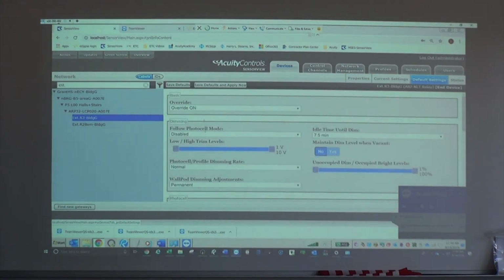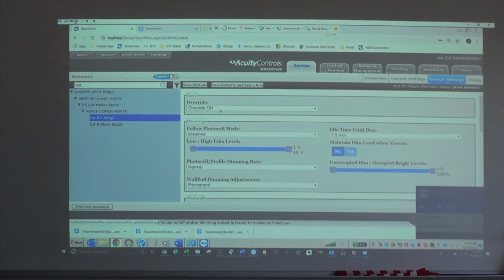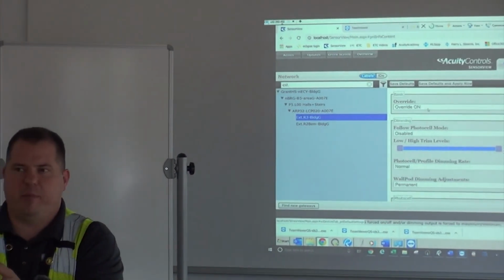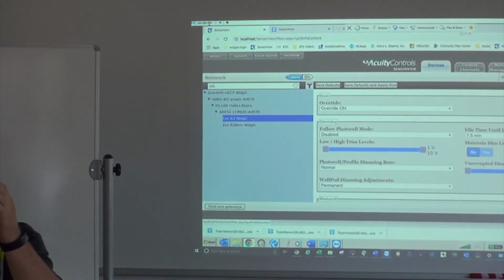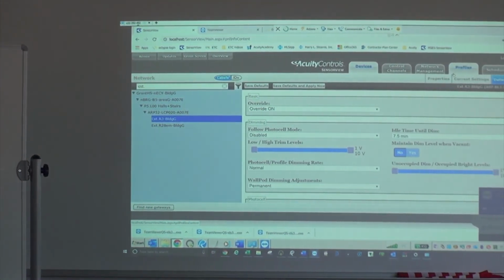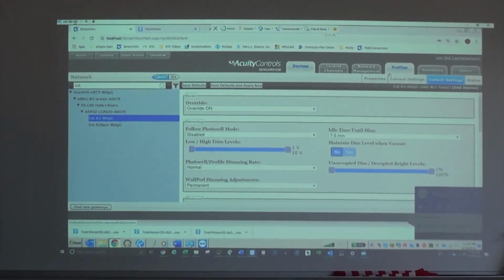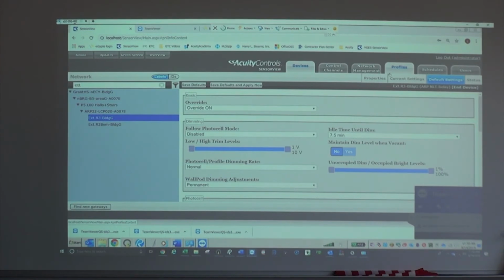So the default state is that override function where the default setting, when there isn't a profile active, reverts back to its default setting. It makes time clock a little more cumbersome because you have to think, this is a temporary override and this is the state. But what we can accomplish with this type of function is this funky hallway thing where during business hours, an unoccupied state only goes down to 50% and up to 100%, and outside business hours it goes to 0 and then up to 100% during occupied.